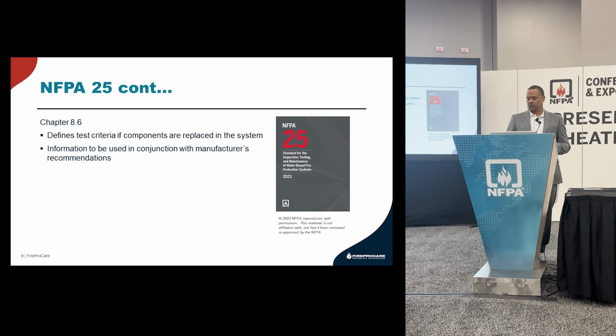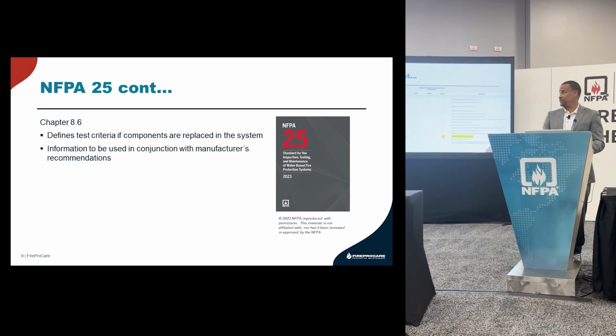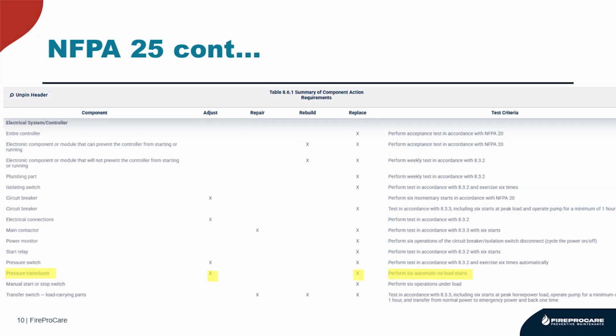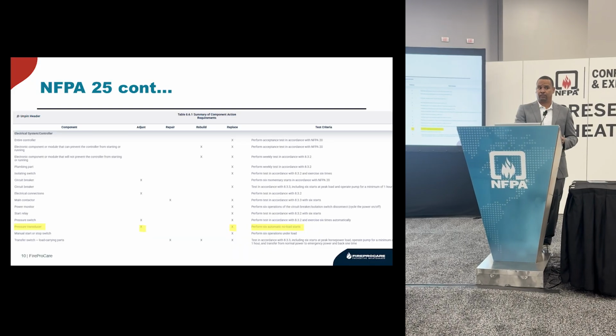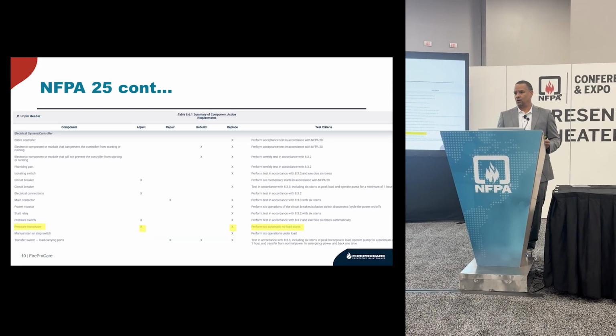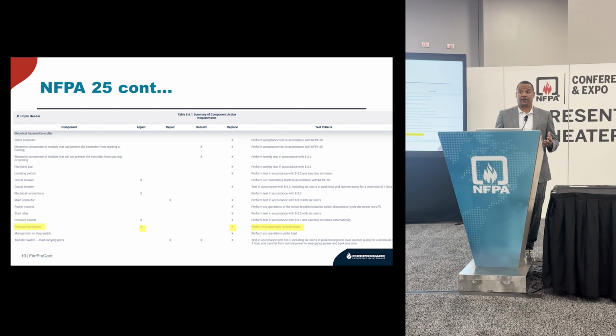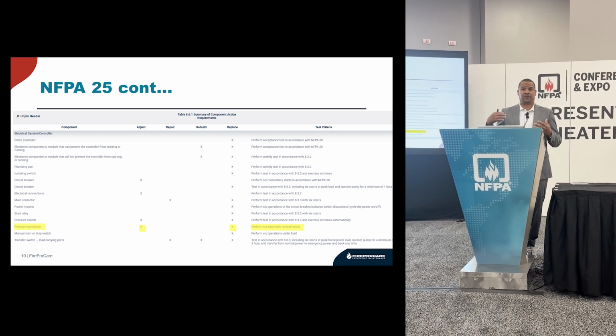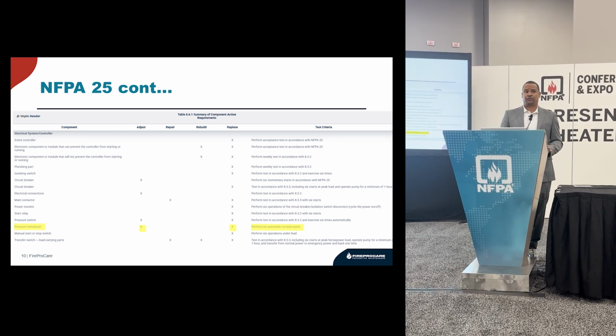So the greatest example would be the transducer, which I know you can't see. I have a hard time seeing it and I'm right here. But I highlighted the transducer, in which case it says, if you adjust or replace the transducer, you need to automatically start and stop that pump 6 times under no load. A lot of people may not know that, but it is required. NFPA 25 has been around for quite some time, and I don't think anyone knows that.